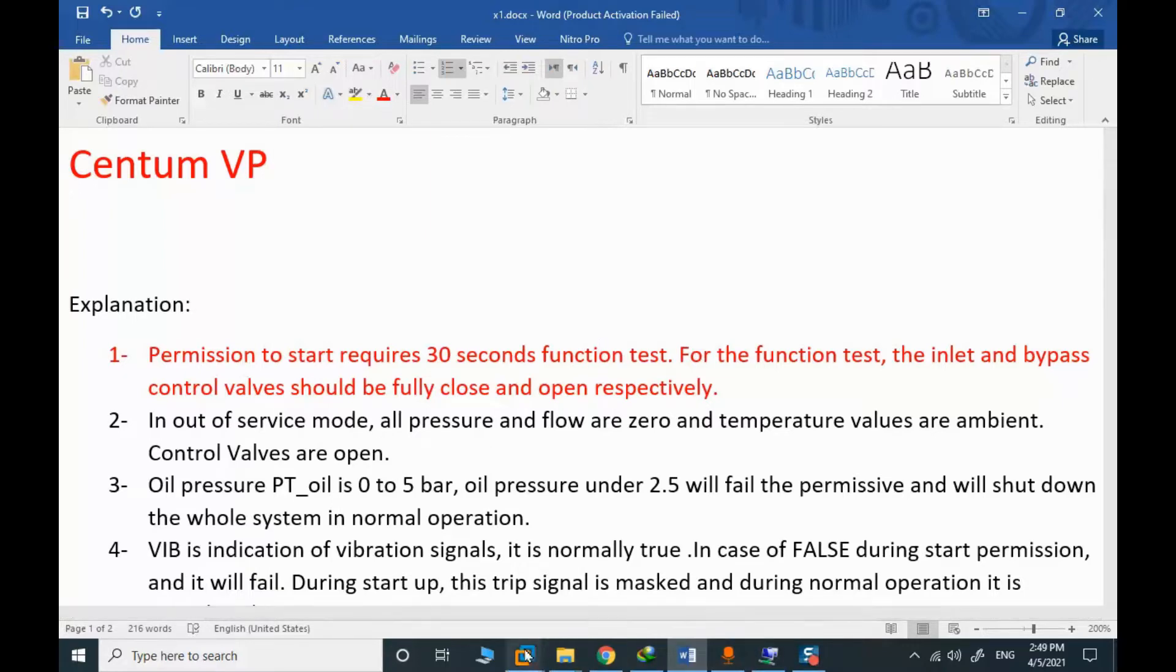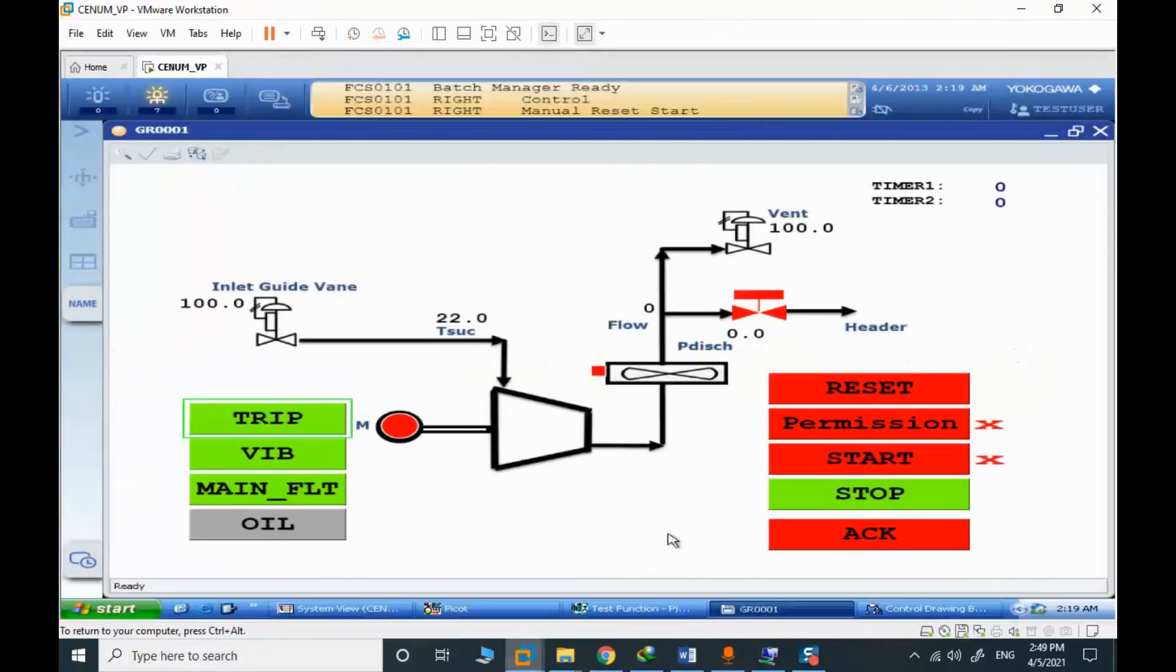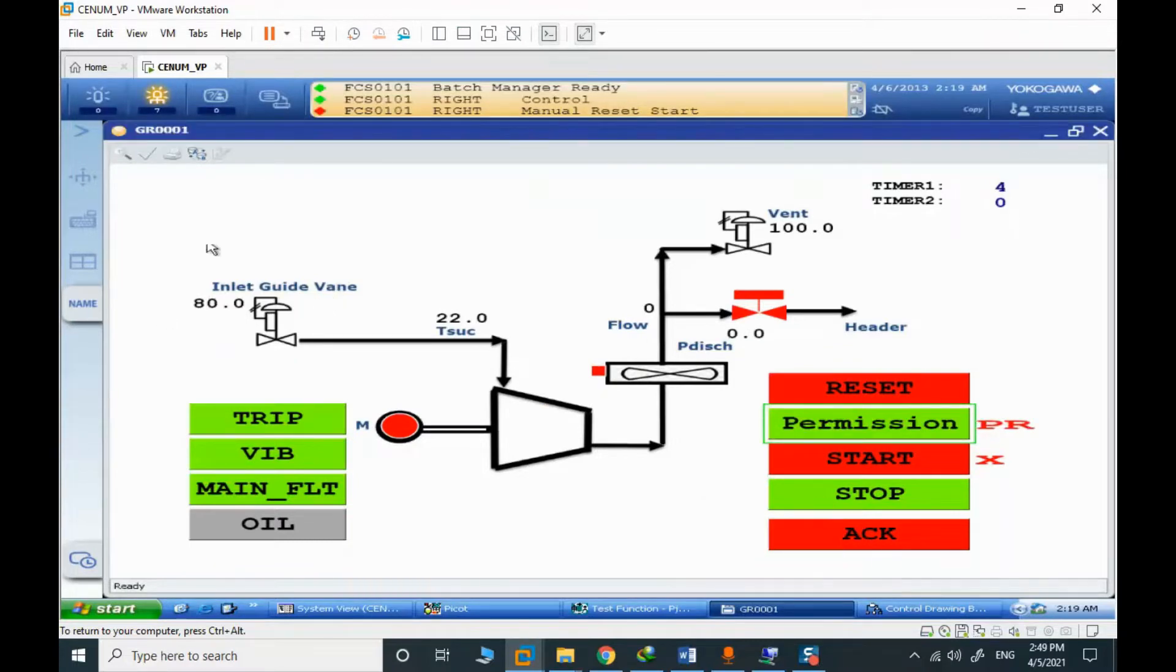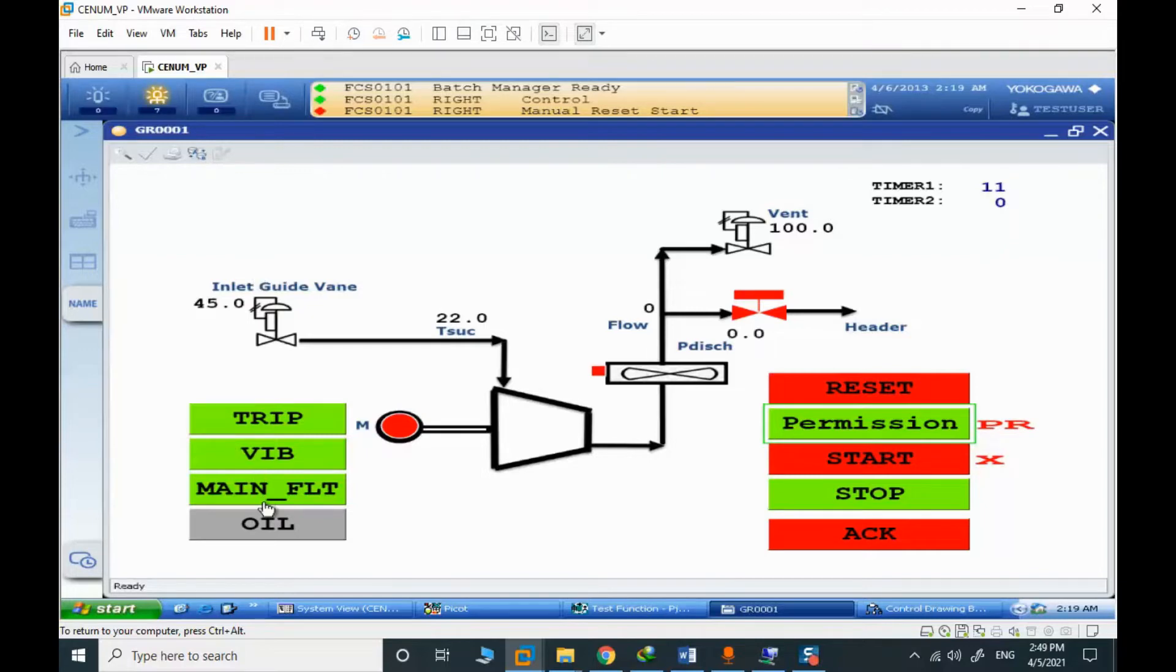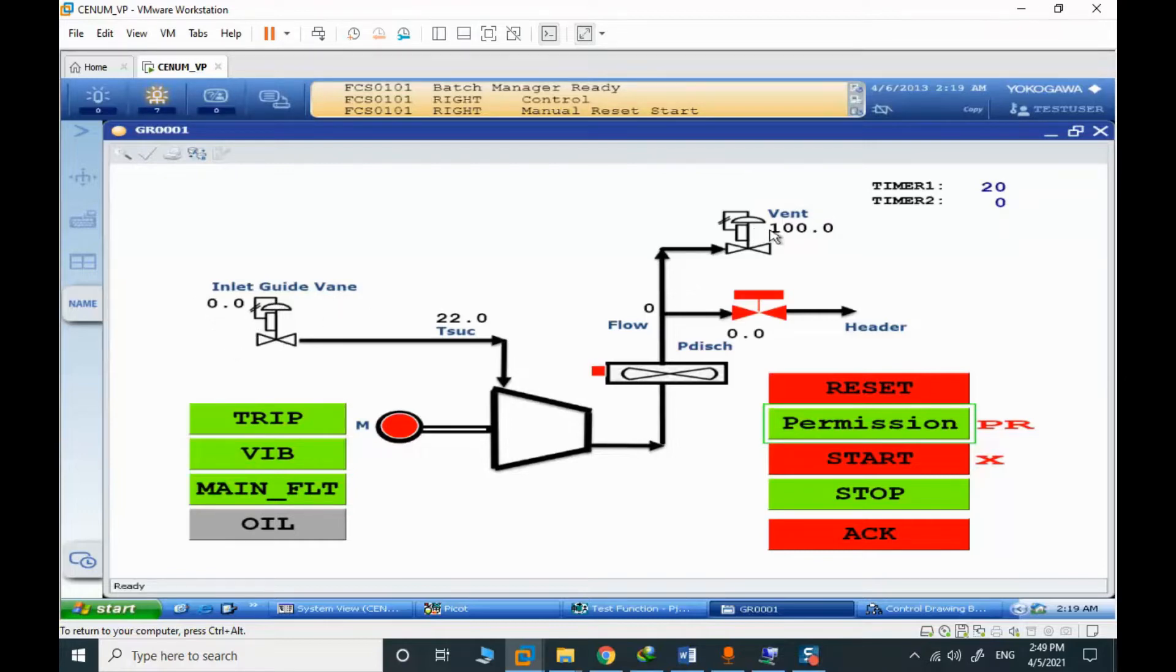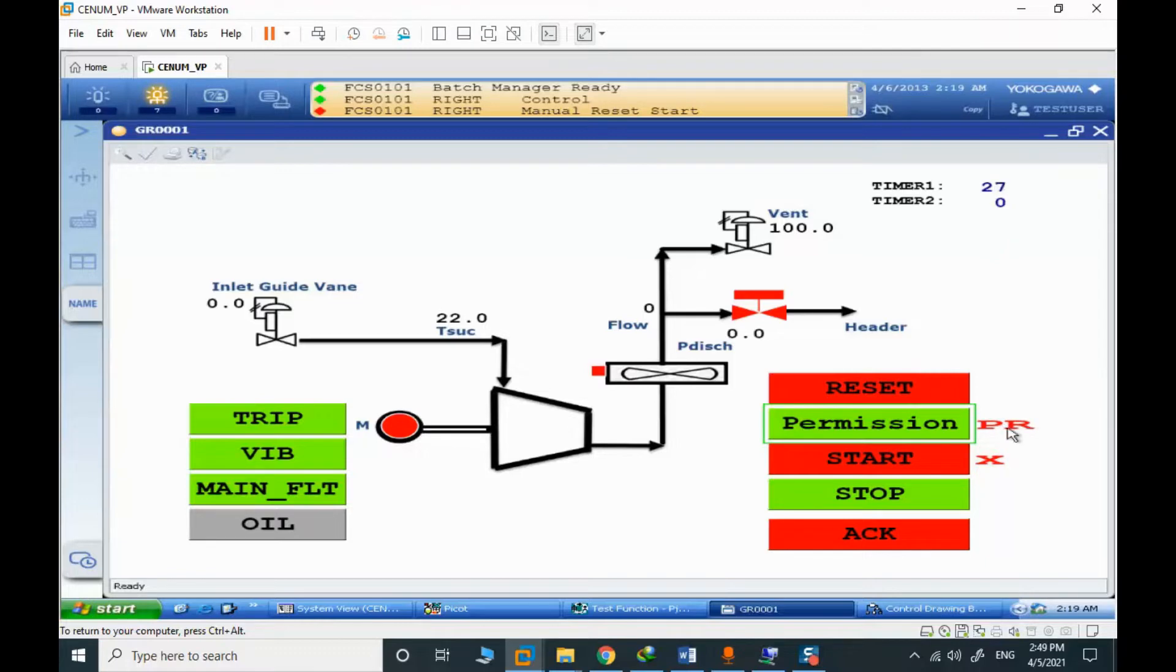We put the compressor in permission to start. We shouldn't have any alarm. You can see the inlet guide vane is closing. We shouldn't have any alarm and everything should be normal. IGV is closing, inlet guide vane is closing and the PCV is open. After 30 seconds, you can see it's in progress. You can see the indication PR means it's in progress.